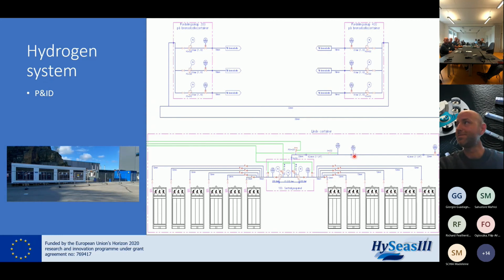I'll be happy to take more questions. Did you guys do a lessons learned with Linde about the connections? We had close communication with Linde when we found all these issues over time. We didn't have a dedicated lessons learned with them, but we had direct communication very closely during this commissioning time. That's also why we had one of these manual pressure reduction valves, this release valve, so that we were able to reduce the fuel pressure over time before we left the site. They came and installed that, and they also replaced some of the reduction valves that seemed to leak more than we wanted. So, warranty claims. But we have had a lessons learned with Linde and also the site owners, after the big leakage. Yes.